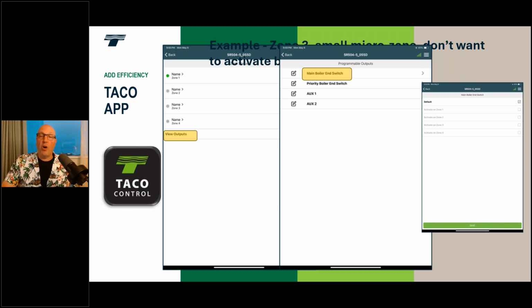But if I were to uncheck the default and turn on zone 1, zone 2, and zone 4, and zone 3 is that micro zone, I'm still going to run the pump for zone 3. It's still going to circulate water, but it will not fire the boiler. We're doing a little zone sequencing here, and it's going to say, all right, there's going to be another zone calling soon enough, and we'll fire the boiler then. If you've got a cast iron boiler here, hey man, let's take those BTUs out of that boiler before we even think about firing it. So this is what I mean on how we can customize it and make it as efficient as possible.